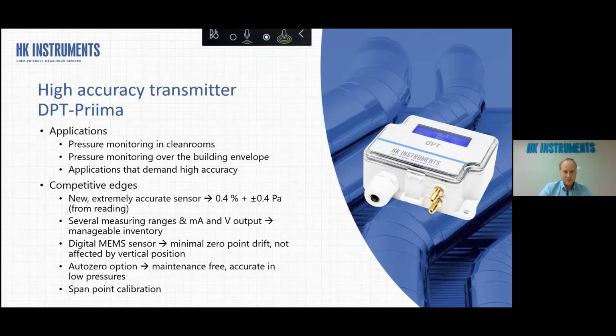And it also has milliamp and voltage output. And this MEMS sensor is not affected by vertical position. And typically clean room DP transmitters are requested not only with the zeroing possibility, but also with span point calibration. So you can do this kind of field calibration by adjusting the span with this kind of potentiometer.